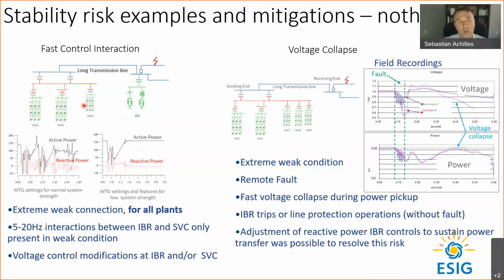that basically caused the system not to be able to recover. Interestingly, if you took these inverter-based resources and had them survive a similar voltage or fault condition with a stronger grid, they would survive. If you did that with the SVC, it would survive. But when you put them together and the system is weak, they start interacting.